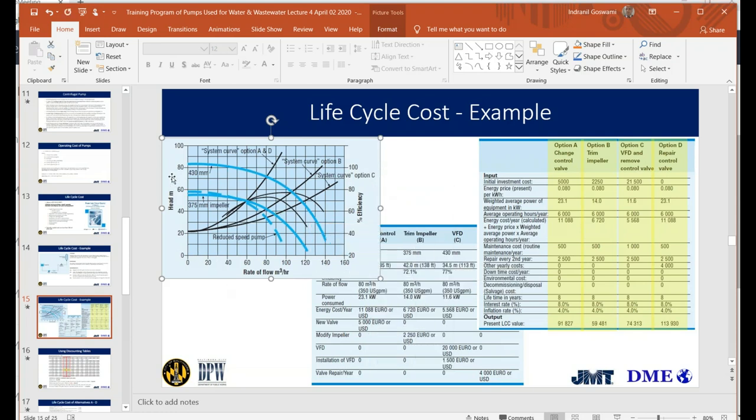So what this is showing is the pump curves, the blue lines, for different size impellers. There's a 375 millimeter impeller curve, that is the lower one, and then there is a 430 millimeter impeller diameter, which is the upper one, which is what we have right now.